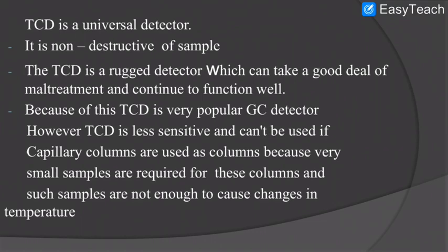Now TCD is a universal detector, and it is non-destructive of the sample. That is, once the gas passes through the resistance wire, it is not affected by it. Only the temperature of the gas may increase and that of the wire may decrease. TCD is a rugged detector which can take a good deal of maltreatment and continue to function well. Because of this, TCD is a very popular GC detector. However, TCD is less sensitive and can't be used if capillary columns are used.